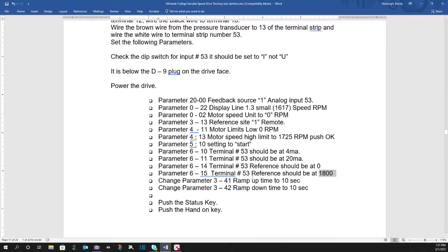And then change our ramp up, ramp down times. It doesn't need to be instantaneous responsive. It can be, because mostly in the real world we're going to measure the suction pressure or the head pressure. We don't have a PID loop on this at all.